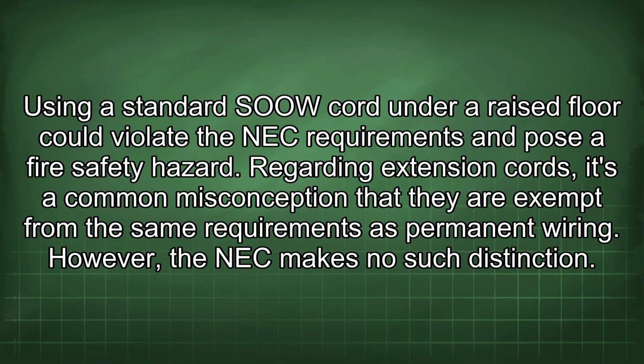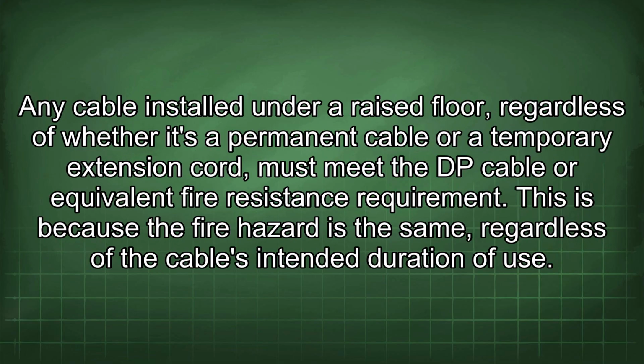Regarding extension cords, it's a common misconception that they are exempt from the same requirements as permanent wiring. However, the NEC makes no such distinction. Any cable installed under a raised floor, regardless of whether it's a permanent cable or a temporary extension cord, must meet the DP cable or equivalent fire resistance requirement. This is because the fire hazard is the same regardless of the cable's intended duration of use.